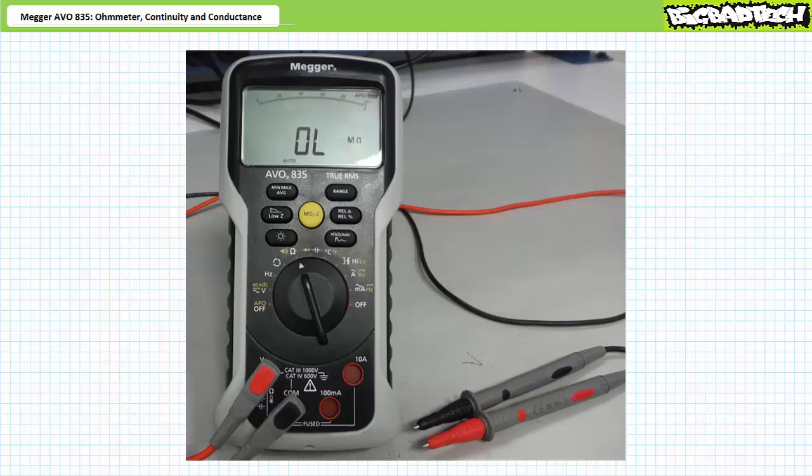The element under test must be depowered and isolated from the system. In the current configuration, the DMM displays OL, which is shorthand for over-limit, indicating the resistance between the two probes is too great to be measured, which implies an open circuit. This is the DMM's way of telling us there is no conductive path between the two probes.